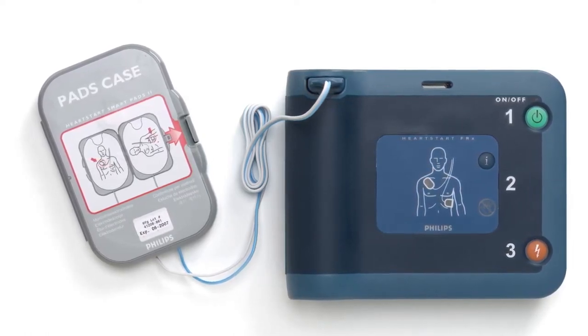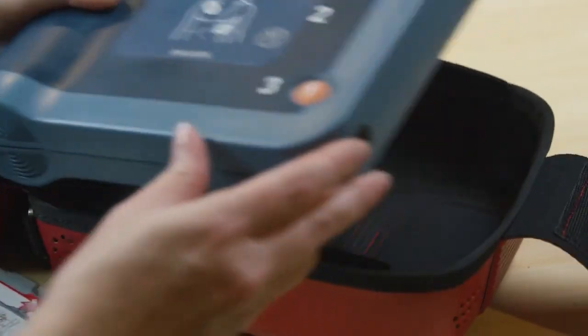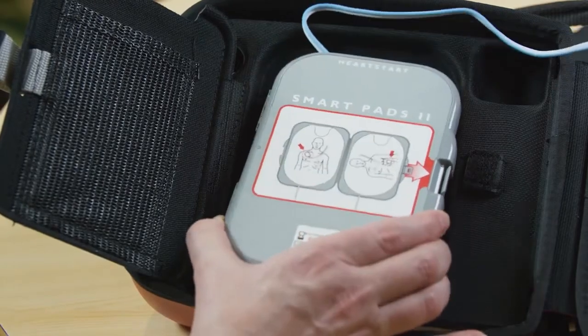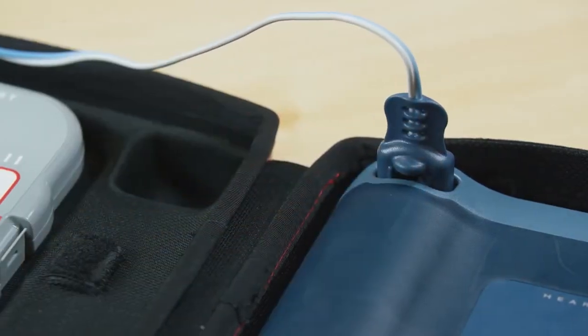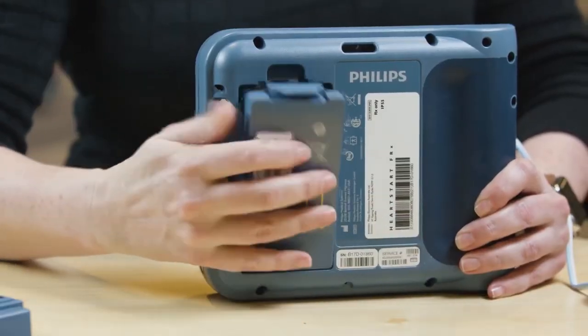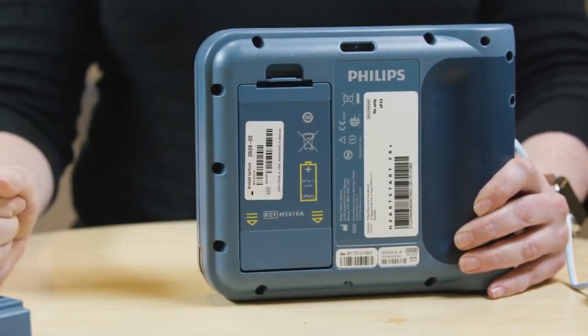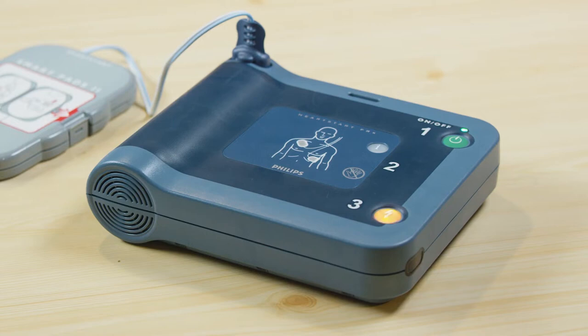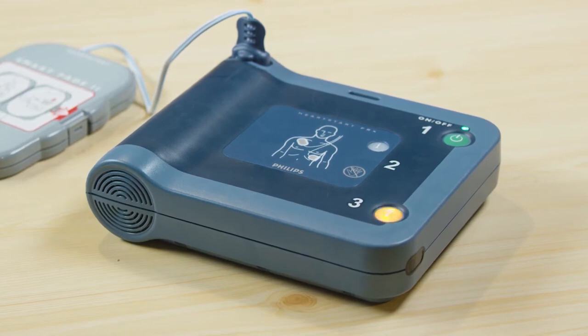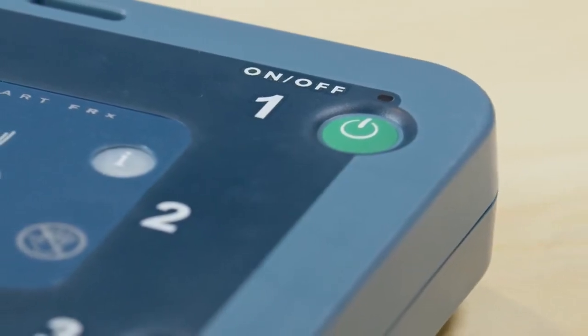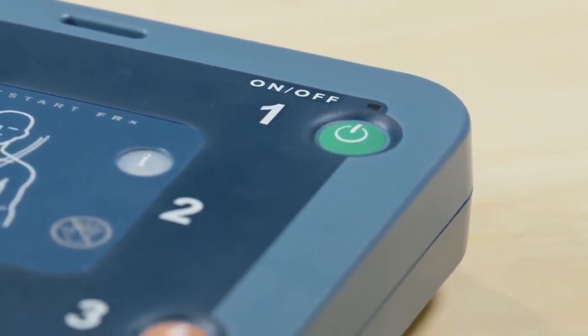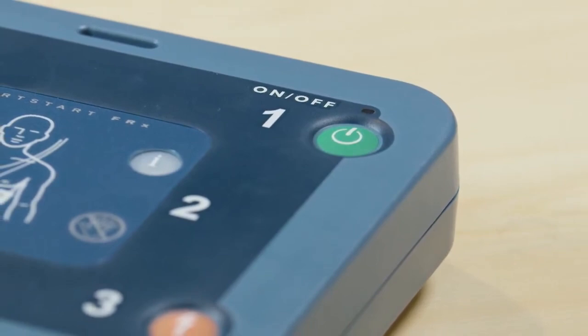In order to perform the initial setup, first remove the HeartStart FRx from its packaging. Then remove the smart pads from the packaging and plug the pad's cable connector into the connector point on the FRx unit. Next, open the battery package and place the battery into the battery compartment. Press firmly on the latch until it clicks into place. Then set the FRx and pads case onto a flat surface and allow the device to run its automatic battery insertion self-test. The FRx will say "Shock Button Test" and prompt you to press the shock button. Next, the FRx will say "On-Off Button Test" and prompt you to push the on-off button. Push the on-off button when instructed to do so. When the self-test concludes, the unit will report the results and then enter standby mode. The ready light will start blinking green, showing that the HeartStart FRx is now ready for use.